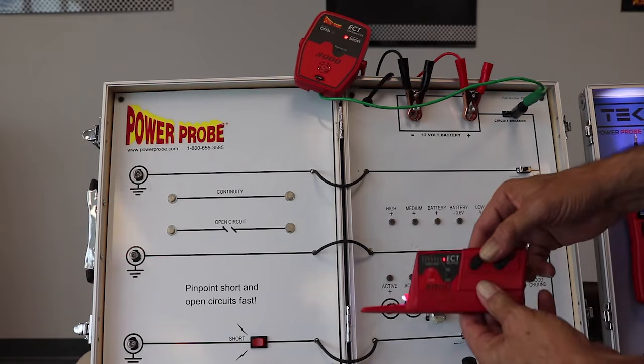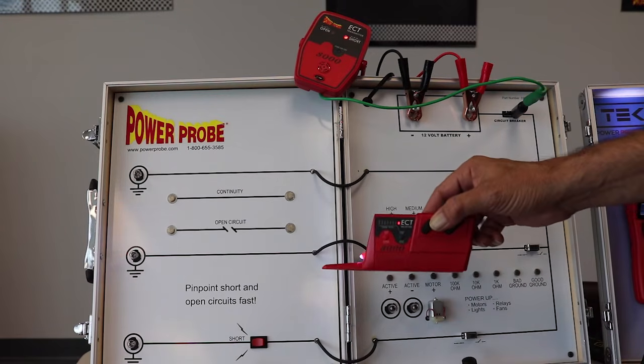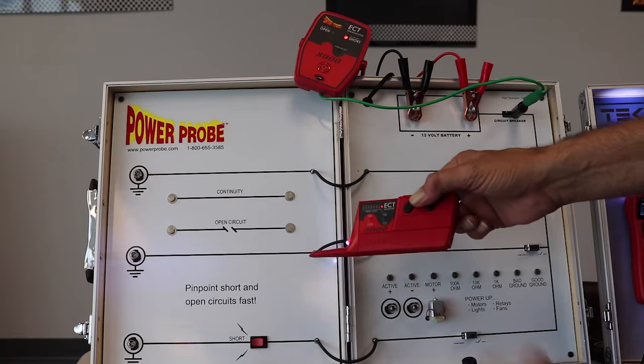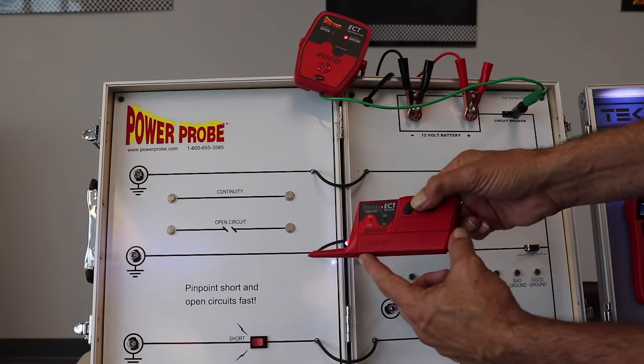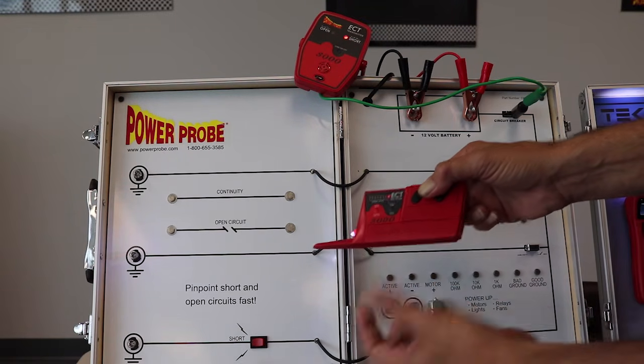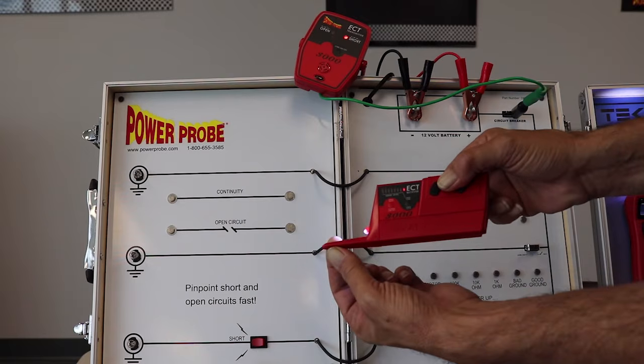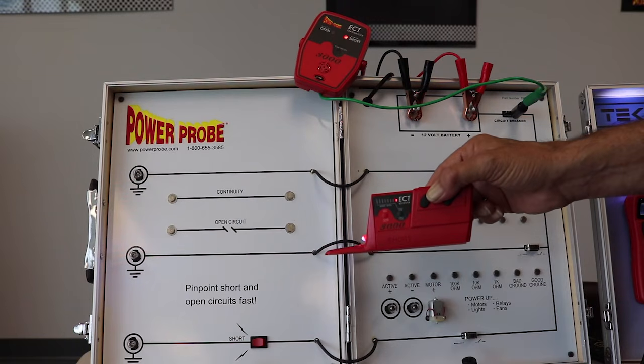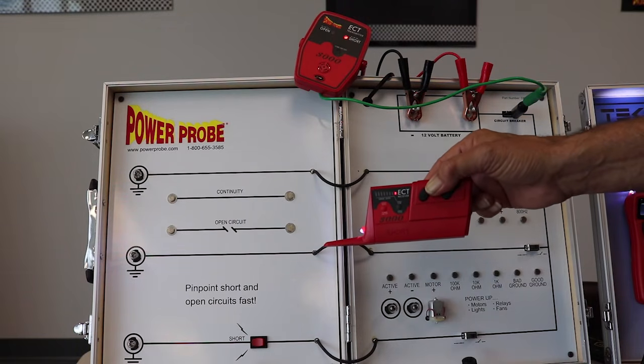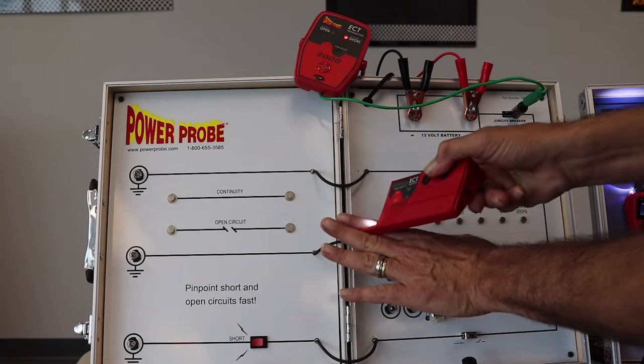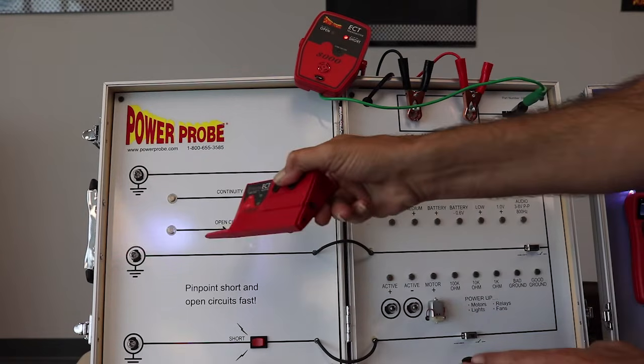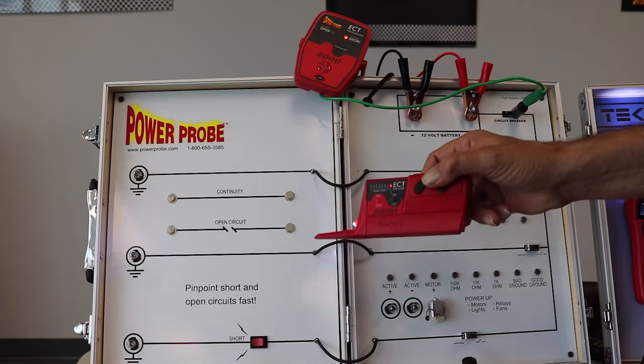Now to really get the best results, you have to understand how this picks up the signal. The short signal is picked up by an antenna in this area of the tool. The open circuit signal is picked up by an antenna in this tip area. The open circuit signal is slightly weaker, so we realize you might have to dive into wire bundles to continue tracking — that's why this has that point on it.